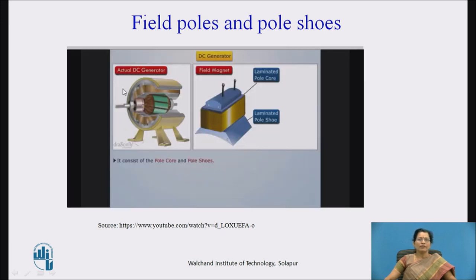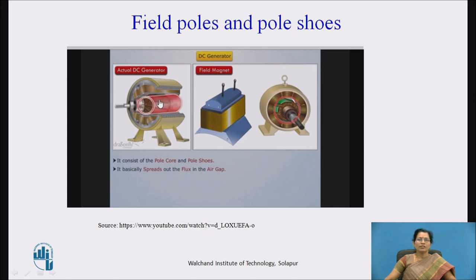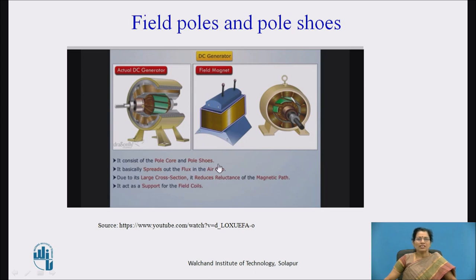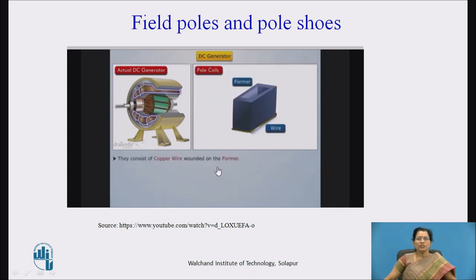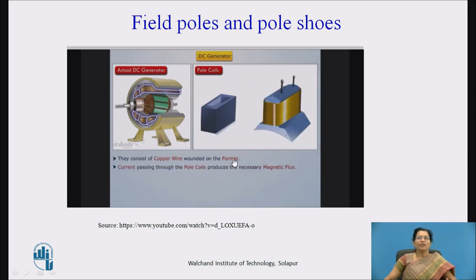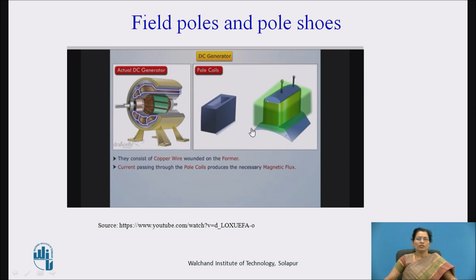Now let us see about the field poles and pole shoes. These are the field poles which create the magnetic field in the machine. This is the core; on that core the winding is placed and a large cross section is provided, giving it low reluctance. When the current flows through that coil, the magnetic field is created around it, and due to the circular shape, that magnetic field is spread out uniformly over the armature core.